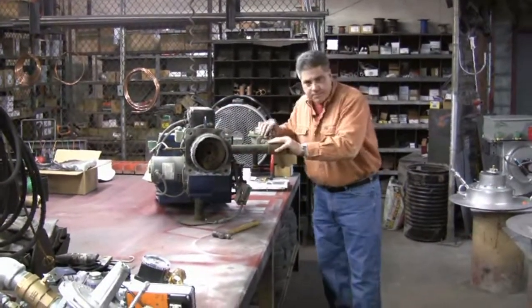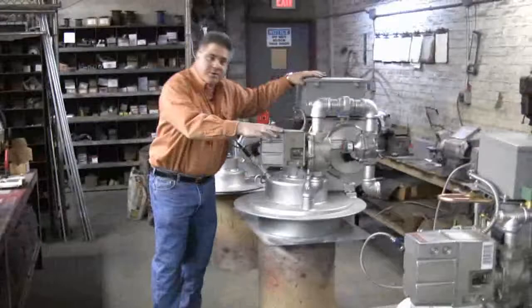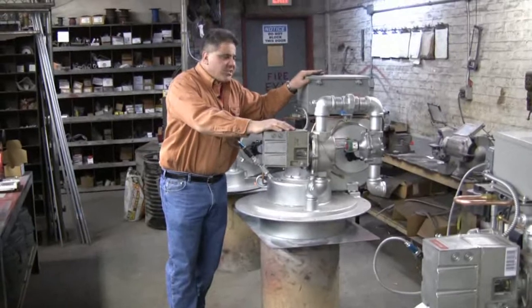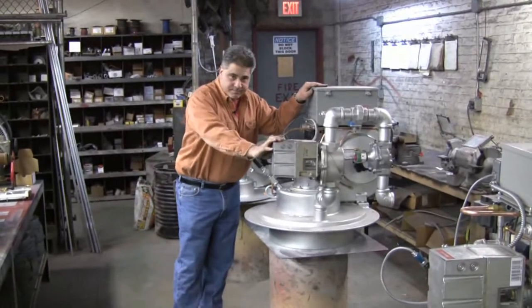We've done tests. We've had stack temperatures on this equipment of over 1,000 degrees. Comparable Infern-o-Therm burners, stack temperatures have only been at 450 degrees. Statistics will tell you that that is where stack temperature should be to burn off moisture and oil impurities in the fuel.